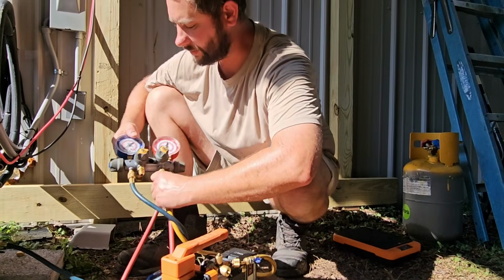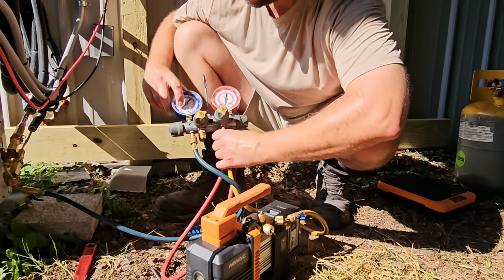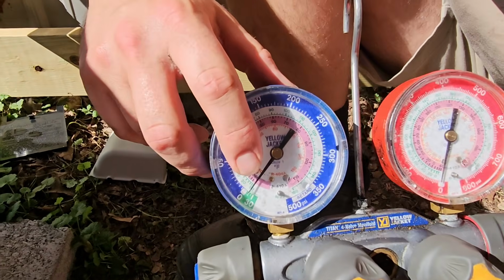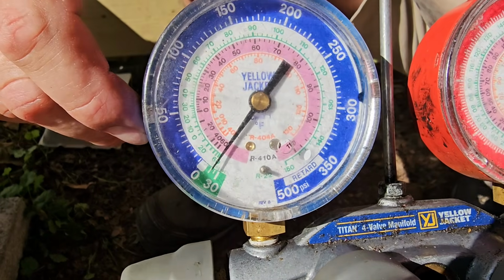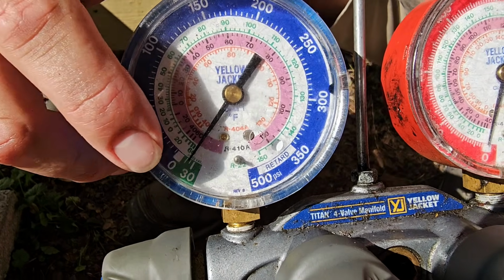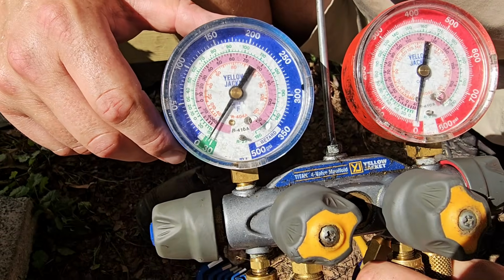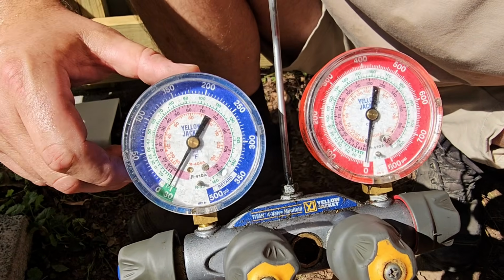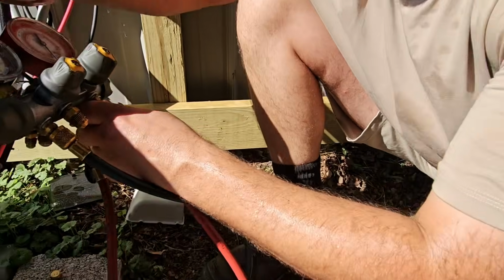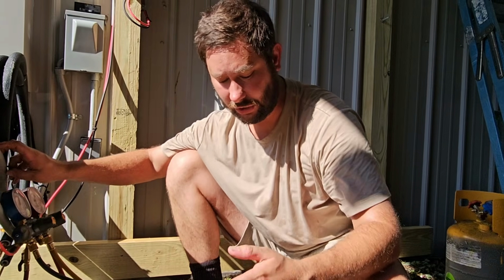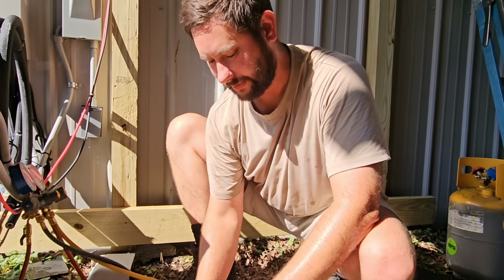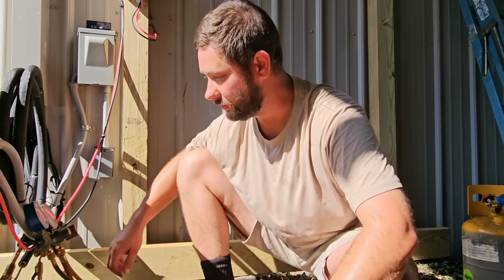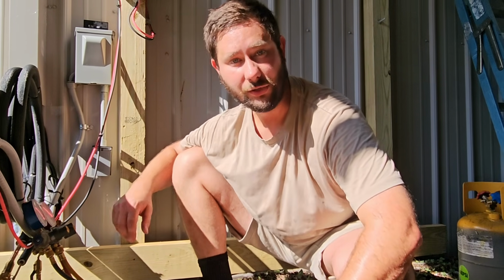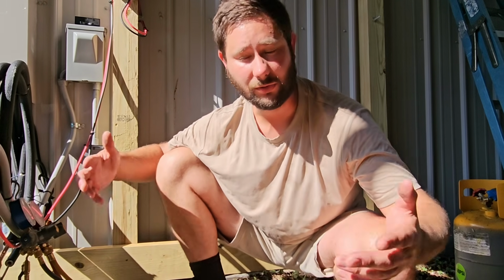Now you'll notice on the gauge, take a look. See how it says 0? But look what's happening. It's pulling down, right? It's going to pull down to 30, all the way down where the 30 is. When it pulls down to 30, we've got to close our ballast. When it pulls down to 30 and you shut your gauges, and you don't hear a sound change in the vacuum pump, that means you've got a good vacuum. Or you look at a micron gauge.